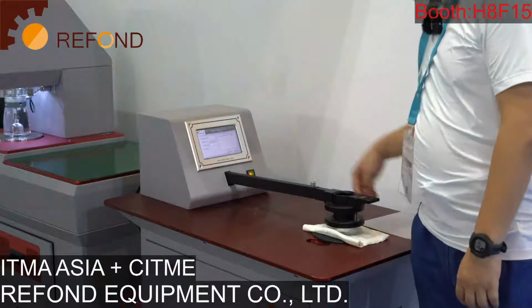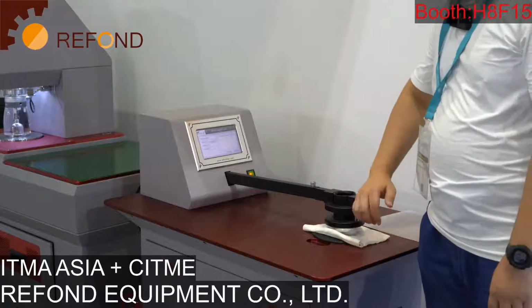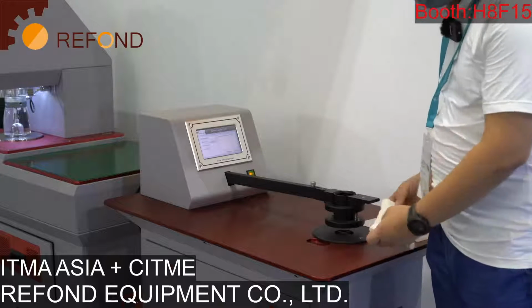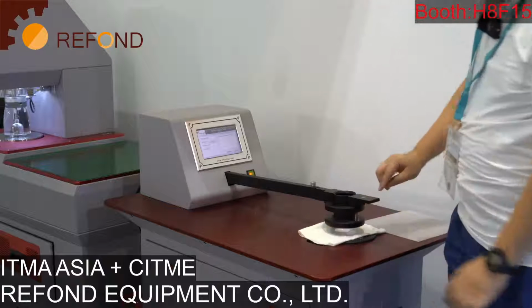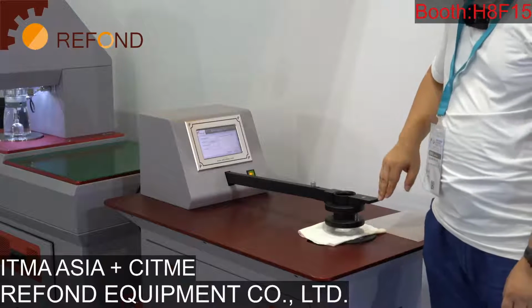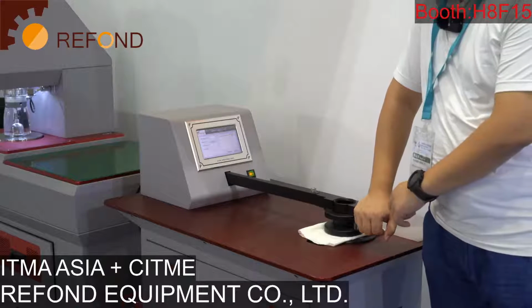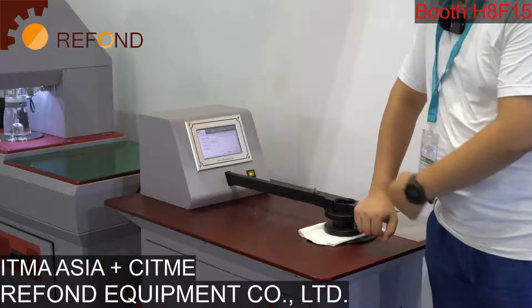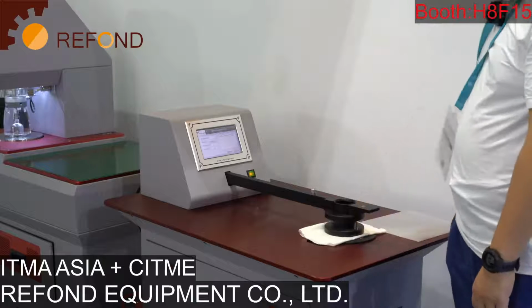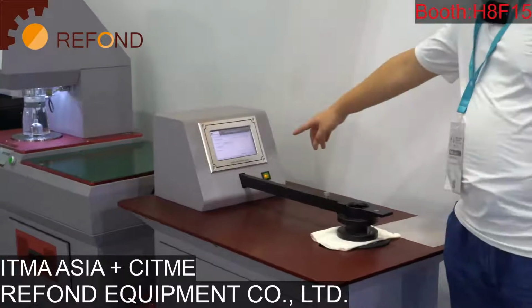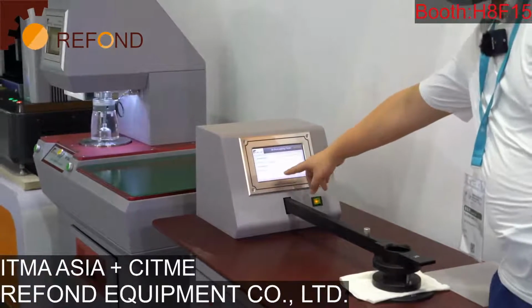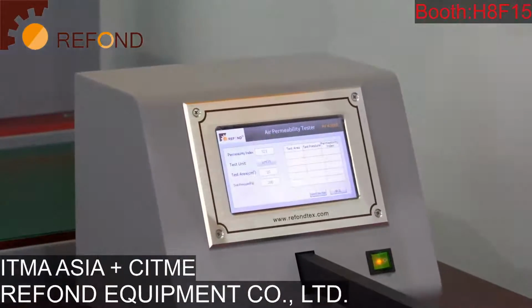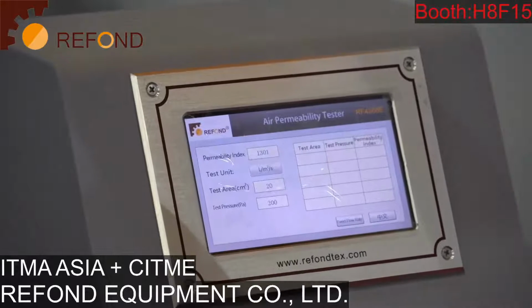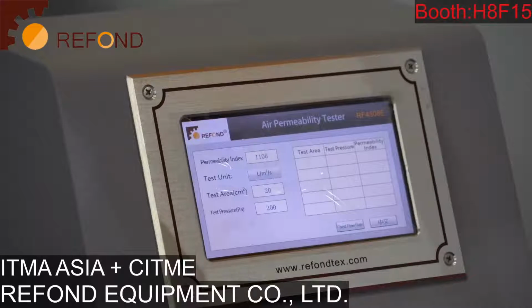Let's do a simple test in a fixed pressure mode. To start the test, you just need to put a specimen in the specimen clamping area and then push down the handle on this bar. Push until you hear a click. That indicates that the test head is automatically locked, and then the test will start. The machine automatically adjusts the flow to meet the target value, target pressure. For different fabrics, the machine can automatically adjust its measuring range so that you do not need to change the measuring range manually.